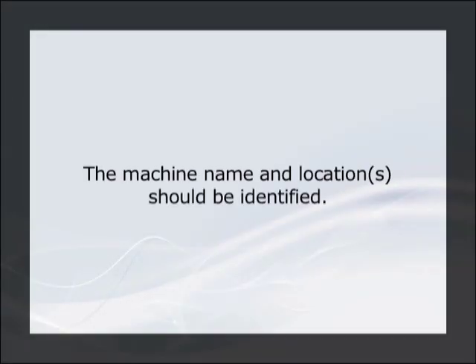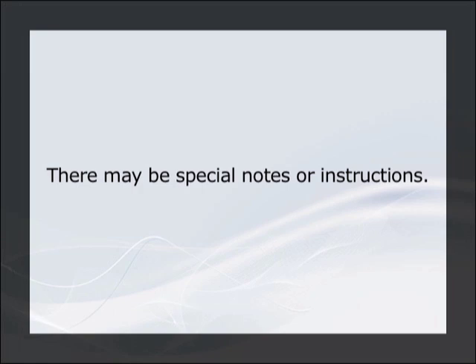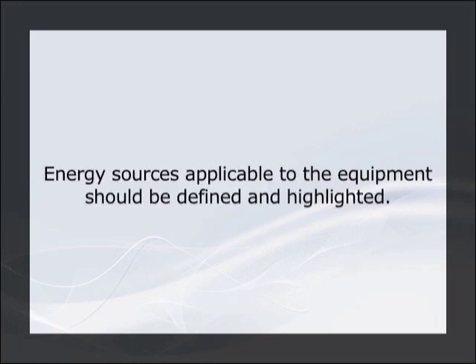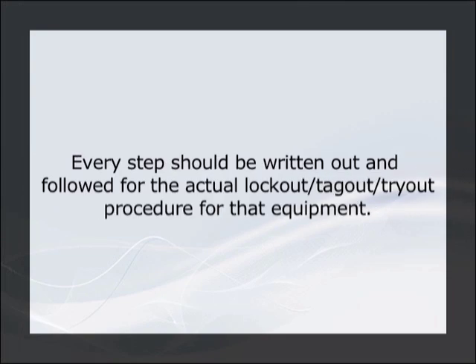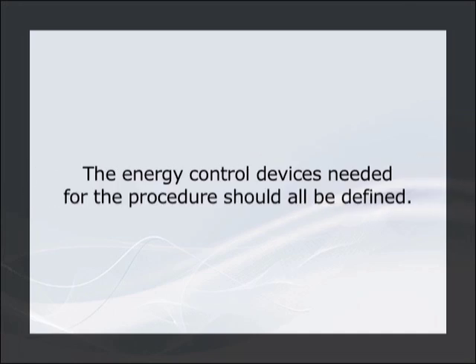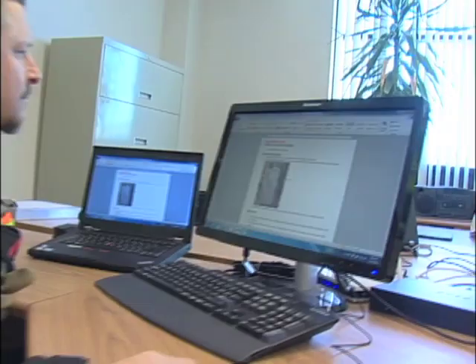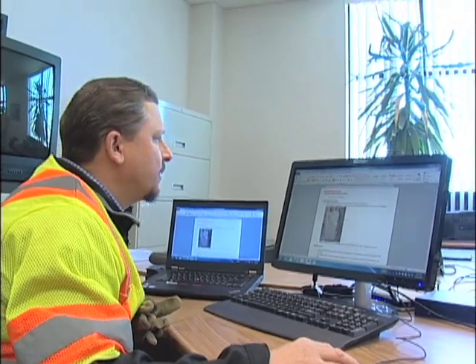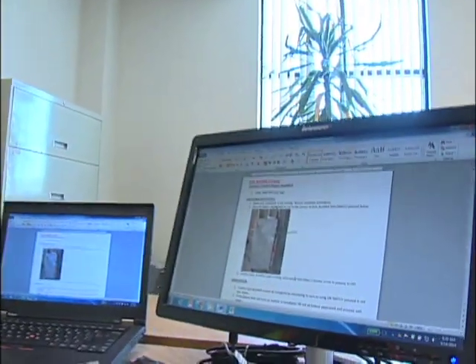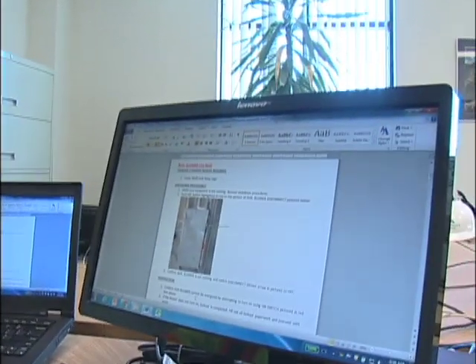The machine name and location should be identified. There may be special notes or instructions. Energy sources applicable to this equipment should be defined and highlighted. Then, every step should be written out and followed for the actual lockout, tagout, and tryout procedure for that equipment. And finally, the energy control devices needed for the procedure should all be very clearly defined. If you don't find the written procedures, stop and immediately consult with your supervisor or plant manager before proceeding.